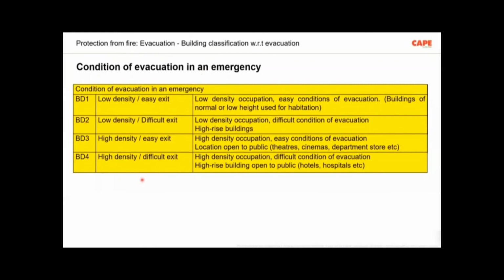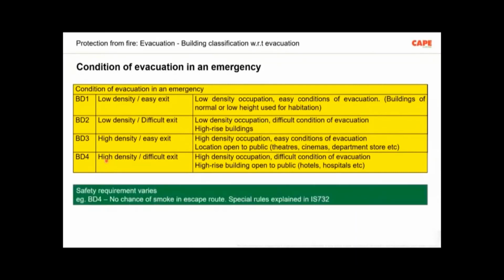Now, one of the conditions we need to understand is that this classification shall be done by the authority involved with fire, for example the fire and safety department. Basically, they have to set that a building more than 15 meters in height and with more than this many people comes under the BD2 category. Then, for example, a hospital of 10 floors comes under the BD4 category. The other categorizations also exist with respect to the content of the building, like explosives or flammable things, and other classifications, for example a hospital where people are unable to move. But I am just focusing on the classification or condition of evacuation in case of an emergency. 4 classifications are made. For each classification, such as BD2, BD3, and BD4, special requirements are there. Special wiring rules shall be adopted while designing and erecting the electrical installation. That is more important for us.